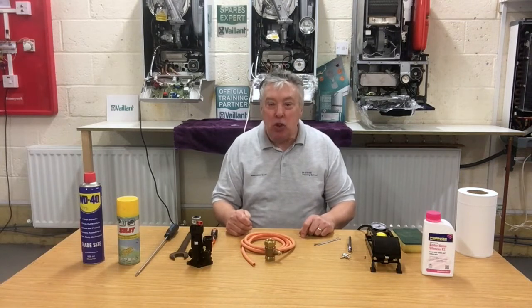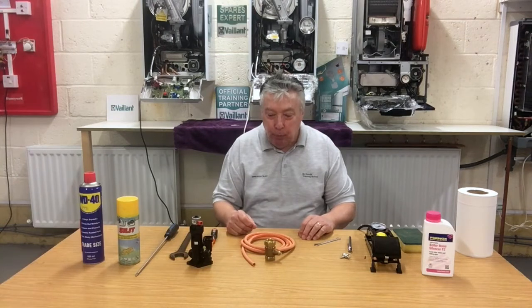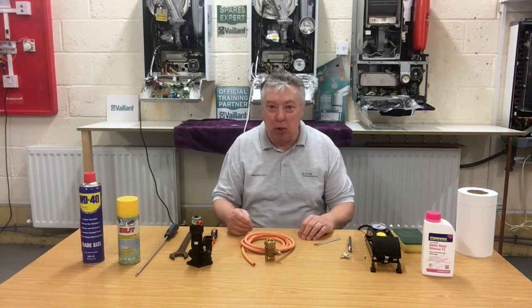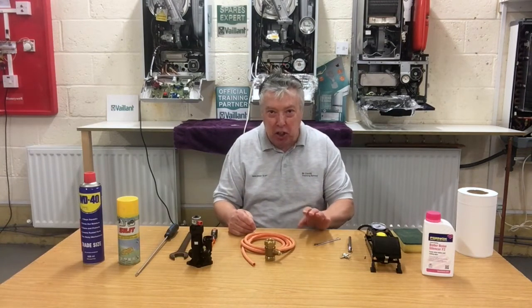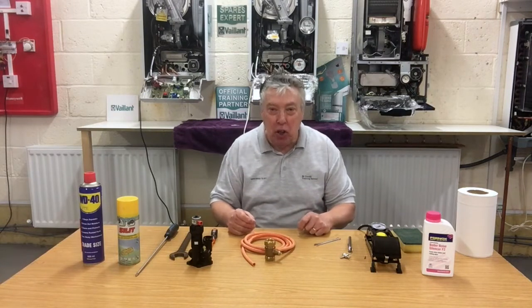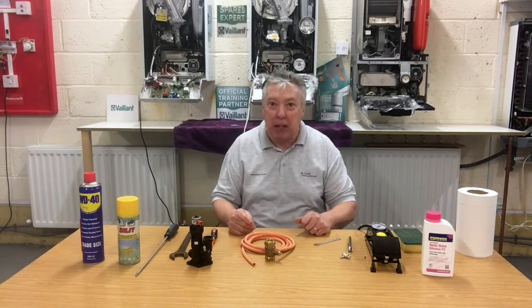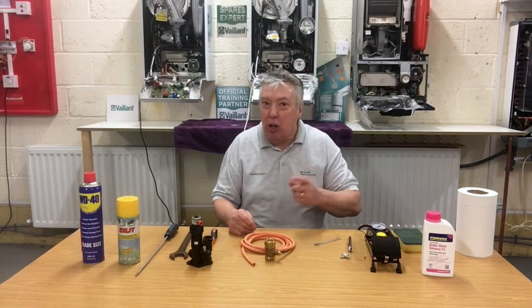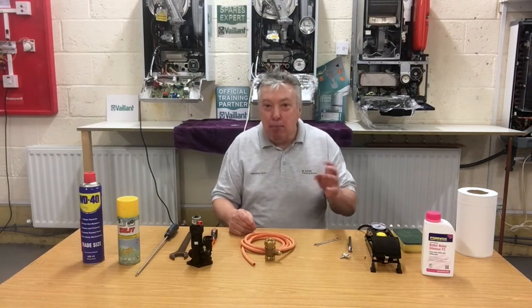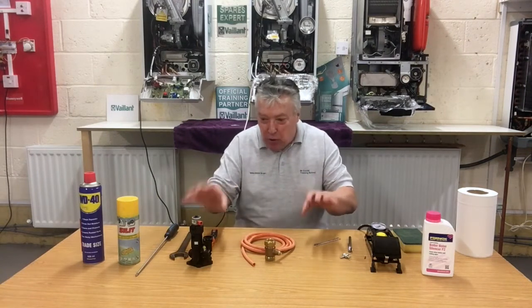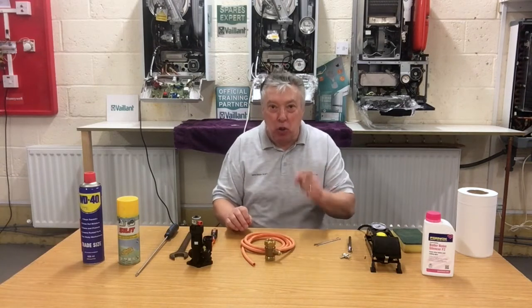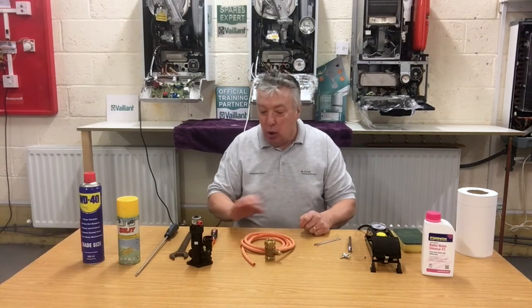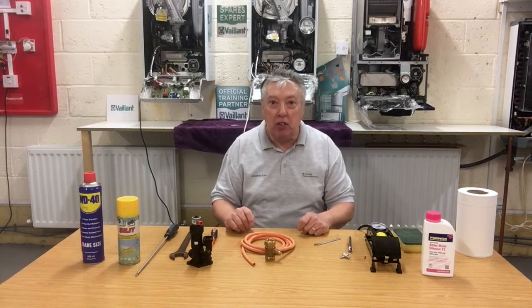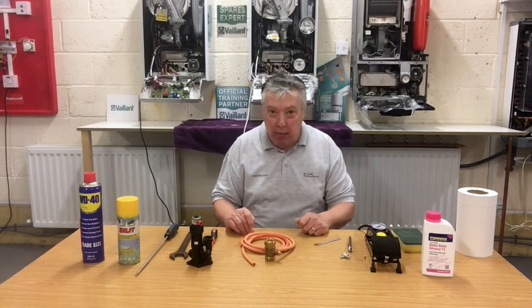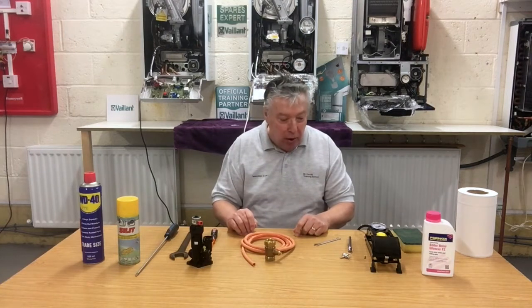Whenever I need to drain down a boiler to change a pump, diverter valve or domestic heat exchanger, I take the opportunity to double check the expansion vessel. That's normally done once a year anyway, but while we're doing this diverter valve change, we'll do that too. The procedure for that is shown in another video I've done, but today we're concentrating on the diverter valve.